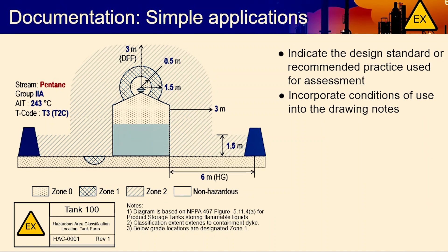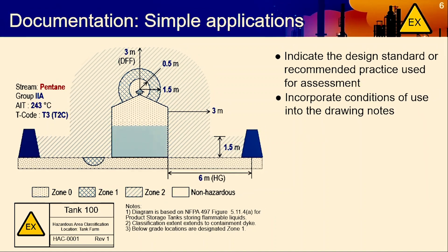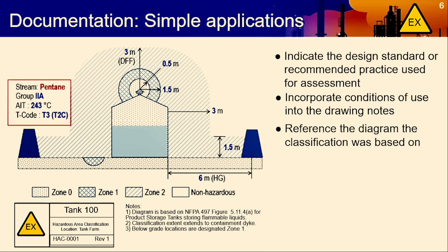The NFPA publication and the diagram are referenced in the drawing notes. The tank contents are indicated as well as the group classification and AIT. This allows the drawing itself to convey the basis for the design.